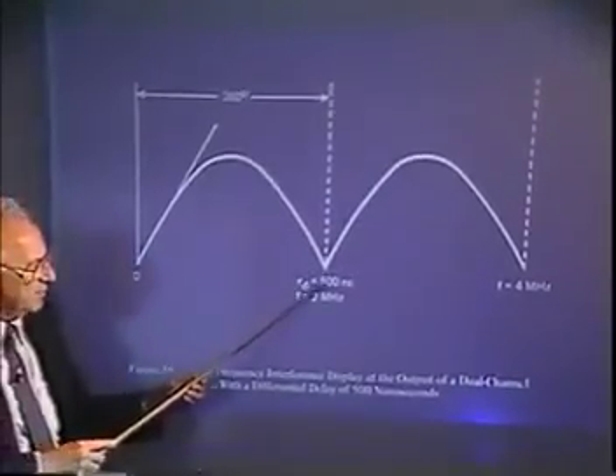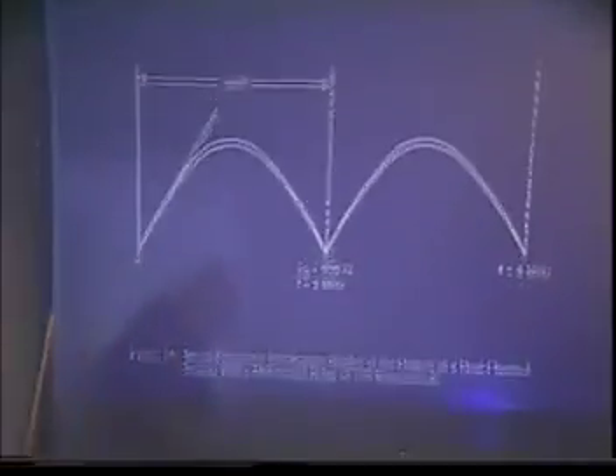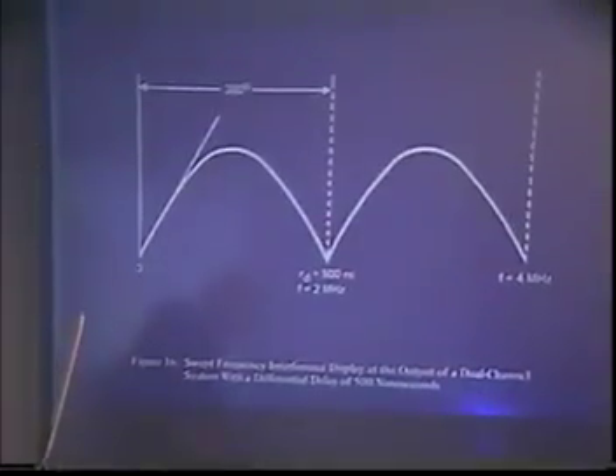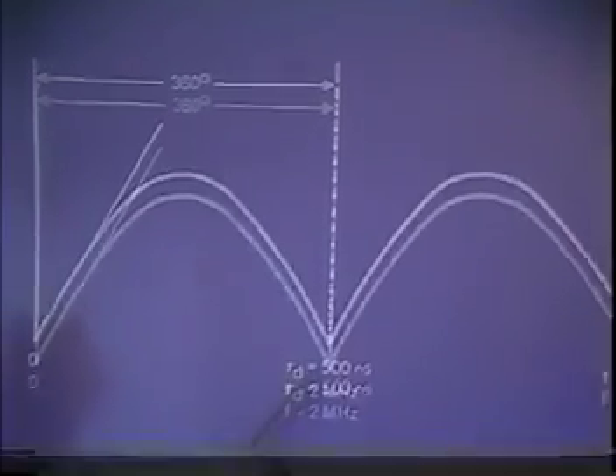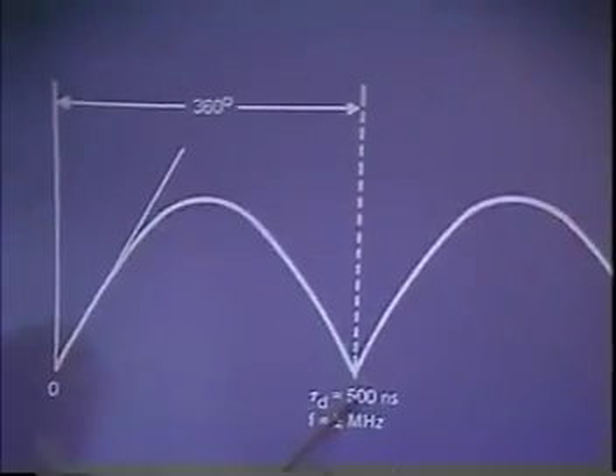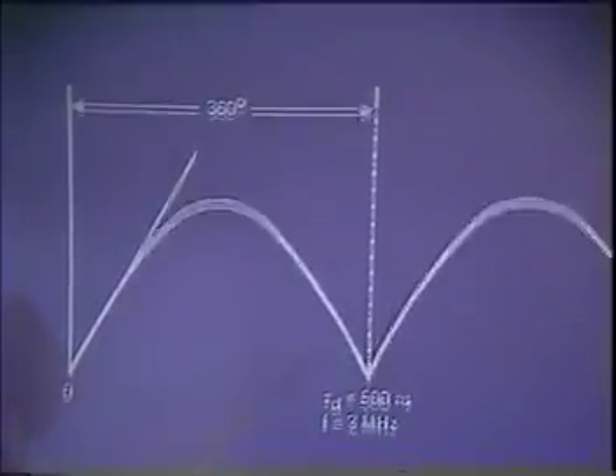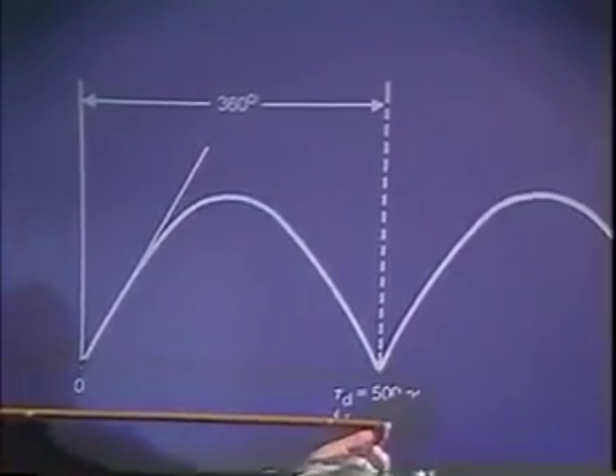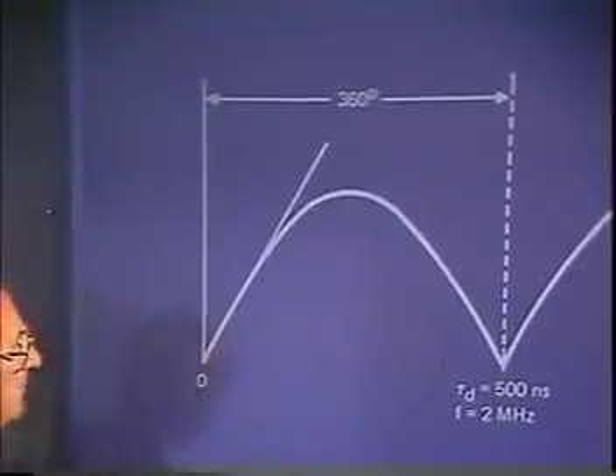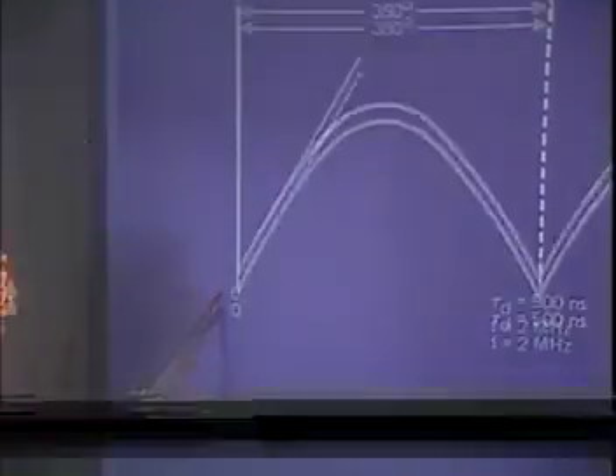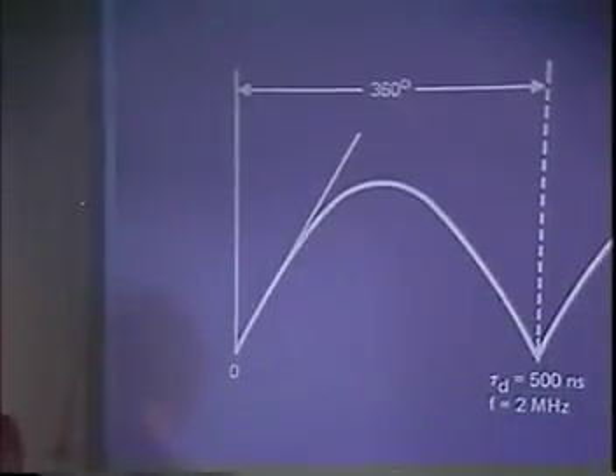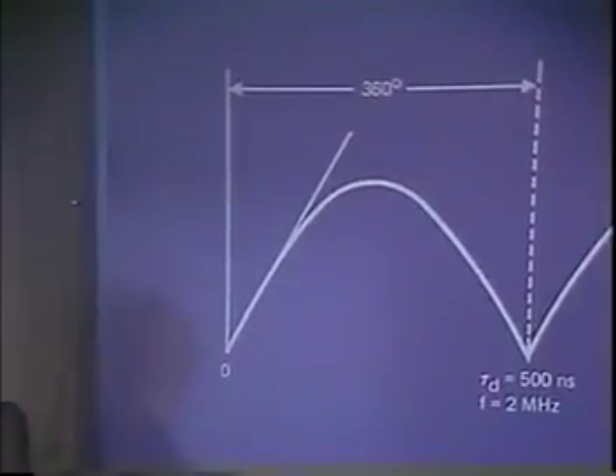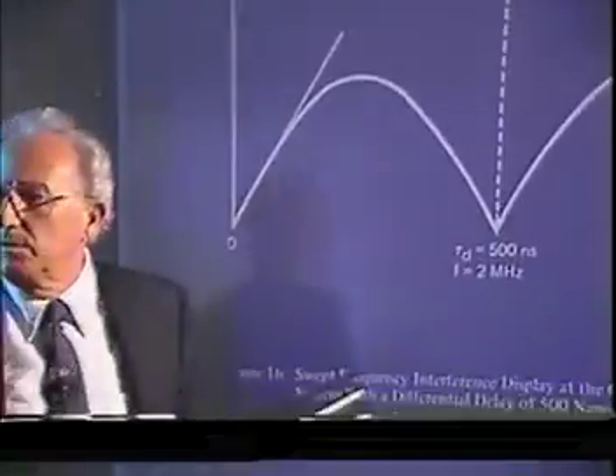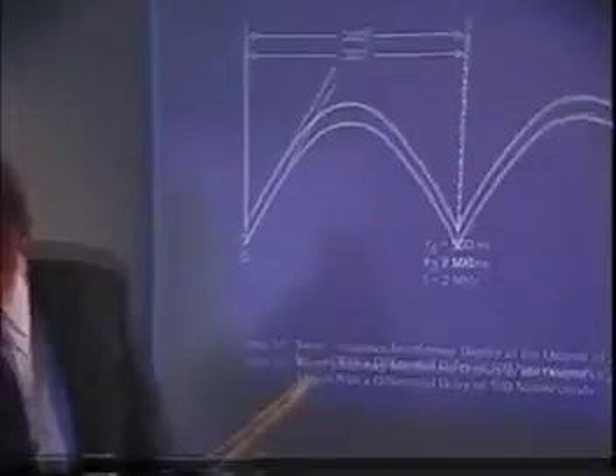But at this point, the time delay in the system is the reciprocal of this. 2 divided into 1 gives you 500 nanoseconds. That means that this line would have been 500 nanoseconds long. Okay? But if you calibrate, this slope here is the only thing that you could use, knowing the volts per hertz of this discriminator. See, because this is essentially the slope of a discriminator. But in a delay line, that's what it looks like.